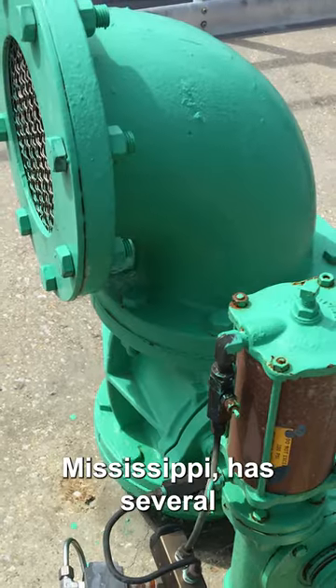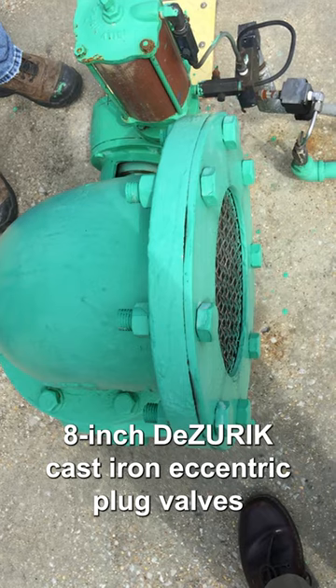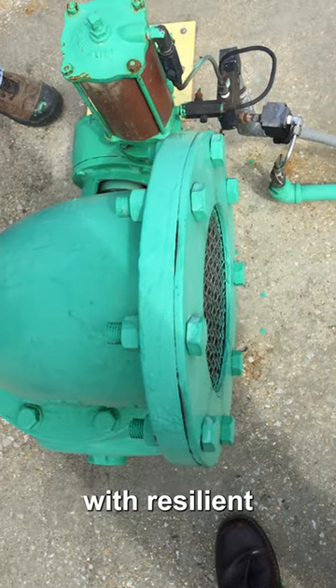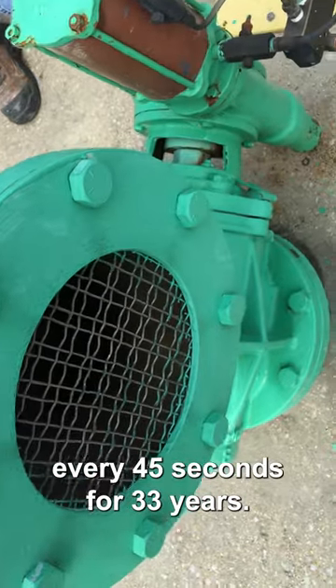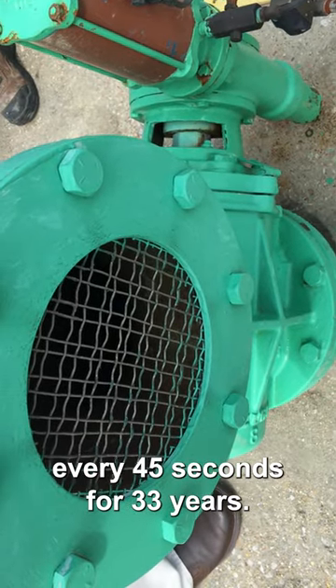A water treatment plant in Tupelo, Mississippi has several 8-inch DeZURIK cast-iron eccentric plug valves with resilient plugs and pneumatic cylinder actuators that have been operating every 45 seconds for 33 years.